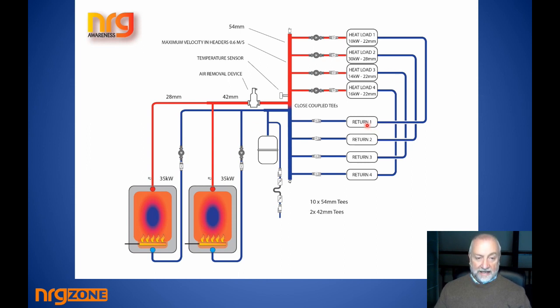So again, if you count up all of your heat loads, you add them together, that's going to be the power of your boiler. Of course, you're going to add on 10 or 15% for pipe heat losses and the like of that, but generally speaking, here we're off with that principle. I'm not suggesting that any one of those zones should not be hot water, or that hot water might be added with a hot water priority situation, which we can talk about. But just now we're taking that there are 4 different zones or 3 different zones, doesn't matter.